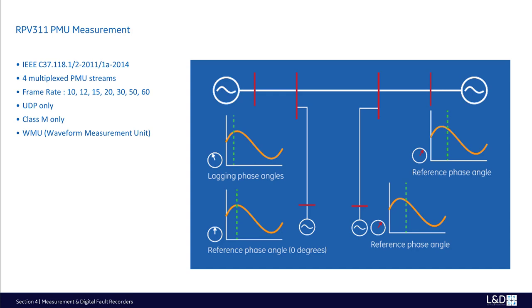RPV311 has a frame rate of 10, 12, 15, 20, 30, 50, 60, and the DR60 has only 50 and 60. For the communication, RPV311 has UDP only, and DR60 has both UDP and TCP. The precision class for RPV311 is M class only, and for DR60 it has M and P classes. And lastly, RPV311 has WMU, waveform measurement unit, for sub-synchronous oscillation monitoring, while DR60 lacks this feature.